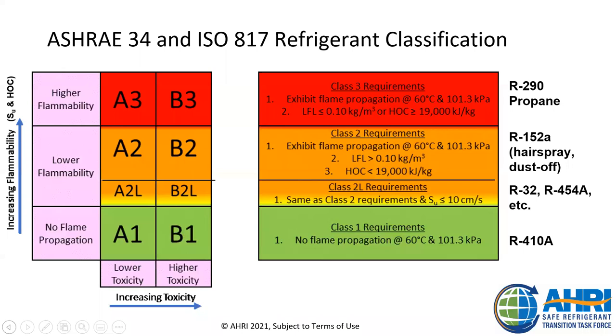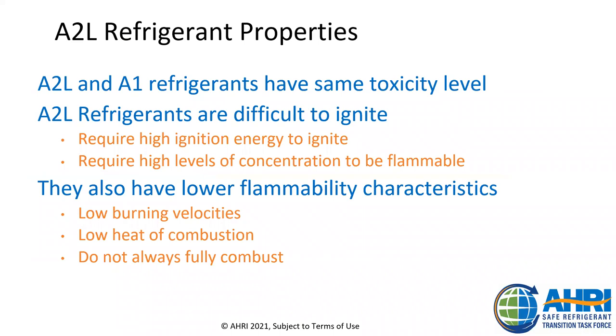Again, as we look at this slide, we can see they're class 2L. They have low flammability and a low burning velocity or flame front and lower heat of combustion. And compared to the other refrigerants that we've mentioned are the A3s such as propane, which is also known as R290. I also want to note another refrigerant that we're not talking about today, but it's been used a lot, R152A, a hairspray propellant, or an A2. So you can see that this refrigerant's been out in the market a long time and it's being used very successfully. So let's talk a little bit again about the A2L refrigerant properties.